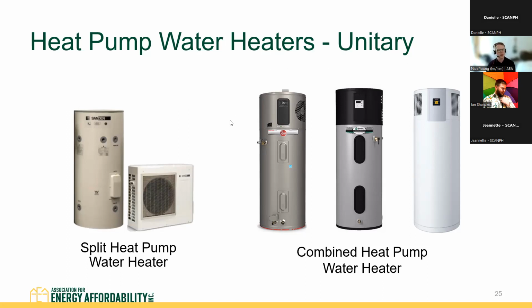These are much less expensive to install in terms of equipment cost. You also don't have to locate a tank and an outdoor unit — it's just one piece of equipment. But the refrigerant they use operates decently well down to about 40, maybe 36 to 38 degrees, and below that it can't really keep up. So they have electric resistance elements in them — that's just electric resistance heating, using about 3 times the energy of the heat pump, much less efficient.